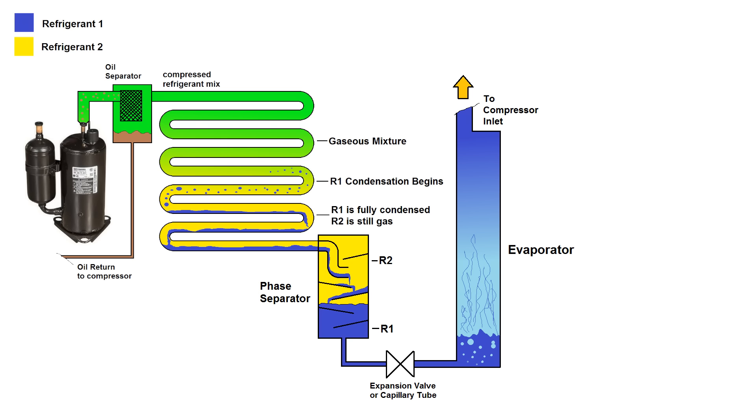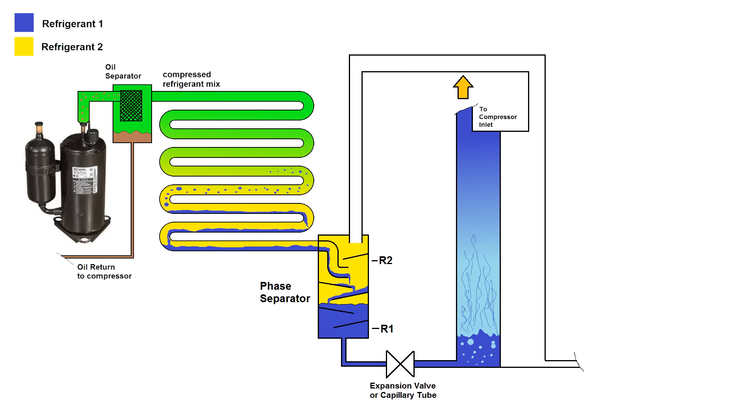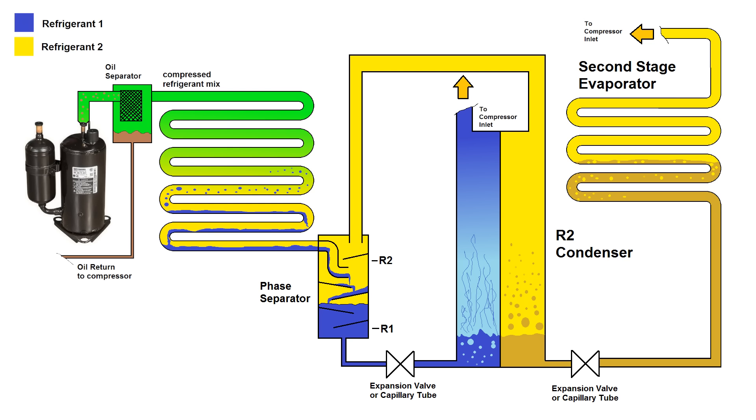And just like with a standard cascade system, the evaporator is actually one side of a heat exchanger. Now at the same time, the gaseous refrigerant two leaves the phase separator through the top and flows into the heat exchanger where refrigerant one is evaporating and getting really cold. The combination of high pressure and low temperature of refrigerant two now causes it to condense, at which point it goes into a separate expansion valve or capillary tube where its pressure drops and it boils in a second evaporator, which is the business end of this whole system.